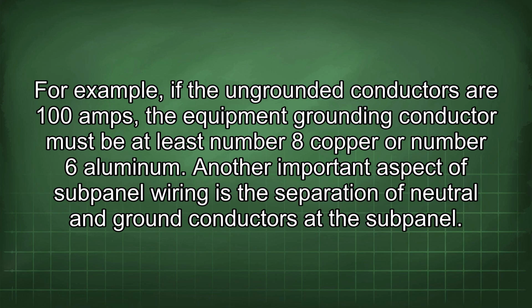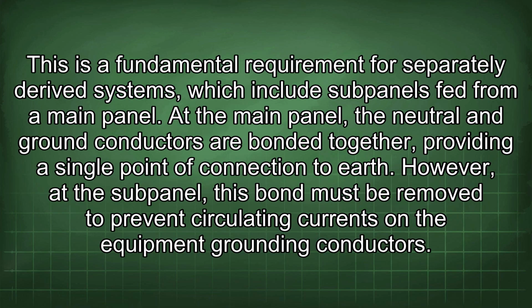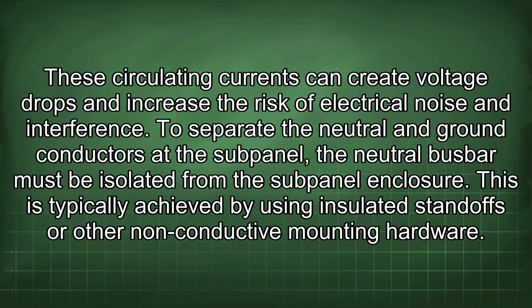Another important aspect of subpanel wiring is the separation of neutral and ground conductors at the subpanel. This is a fundamental requirement for separately derived systems, which include subpanels fed from a main panel. At the main panel, the neutral and ground conductors are bonded together, providing a single point of connection to earth. However, at the subpanel, this bond must be removed to prevent circulating currents on the equipment grounding conductors. These circulating currents can create voltage drops and increase the risk of electrical noise and interference.